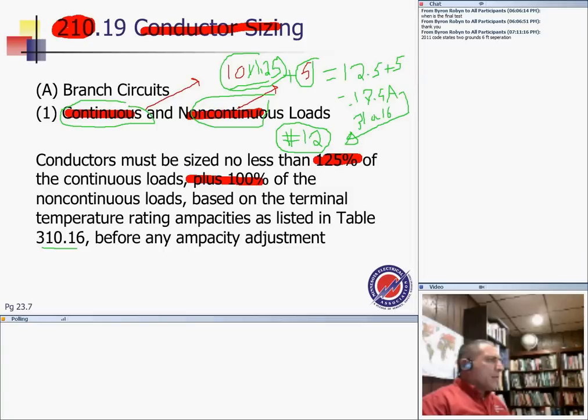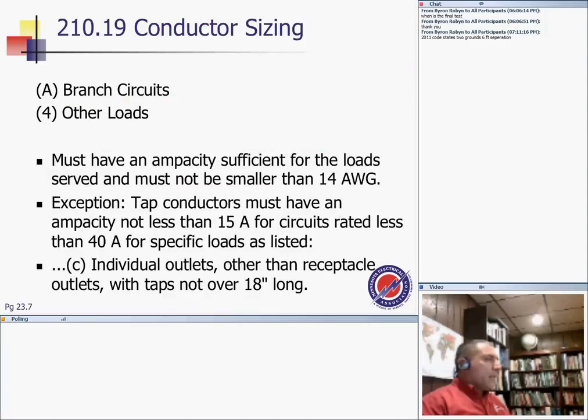A continuous load is a load that can run at full load for 3 hours or more. At full load, not partial load, full load. If you have a machine that can run for 3 hours or more at full load, then this is a continuous load. When you use a branch circuit for it, you have to multiply by 1.25. Examples of this, guys, are all air conditioning. All motors are considered continuous load. Capacitors are considered continuous load. Lighting systems are considered continuous load, and so forth.